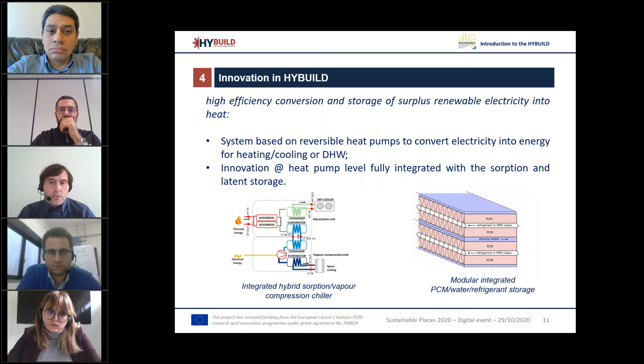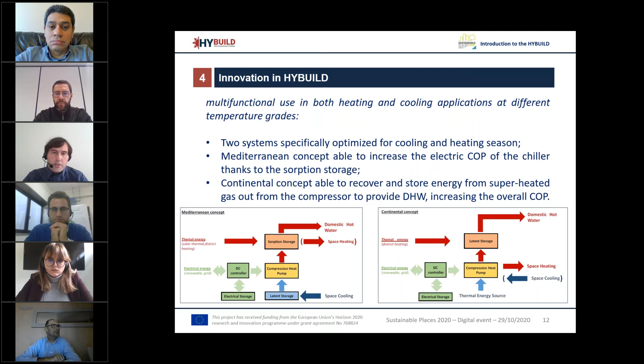Regarding multifunctional use in heating and cooling, both systems can provide either cooling or heating, although the Mediterranean concept was specifically optimized for cooling, with an increased COP of the heat pump thanks to the sorption storage. In both the Mediterranean and continental concepts, the idea is to recover and store the energy from the superheated gas coming out of the compressor of the heat pump, and this heat stored in the PCM can later be used for domestic hot water, increasing the overall COP of the system thanks to the latent storage.